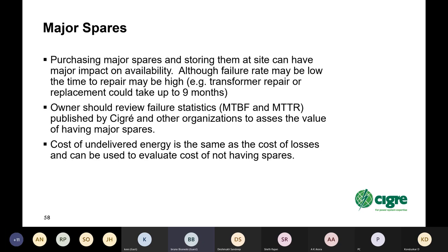The owner should review failure statistics, mean time between failure and mean time to repair, published by CIGRE and other organizations, to assess the value of having the major spares. And that should be done before you complete your specifications, so that you can decide whether you want to include the major spares in the spec. Usually it's cheaper to buy them in the spec rather than later. On the other hand, if you find that the possibility of failure is so low that you can absorb the risk, of course you can save some money. And one of the tools for looking at whether it's any value in having major spares is the cost of undelivered energy, and it's really based on the same as the cost of losses, and that can help you evaluate whether or not having major spares is worthwhile.